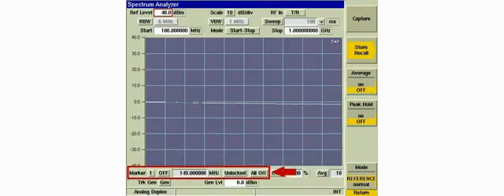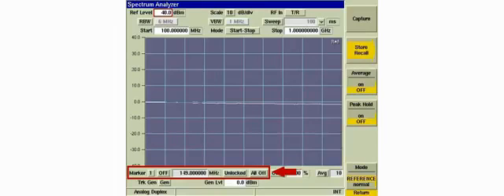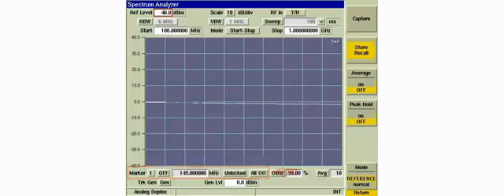Our radio's transmitter frequency is 380.025 MHz, so we'll use a marker to find out how much loss the cable has at that frequency.